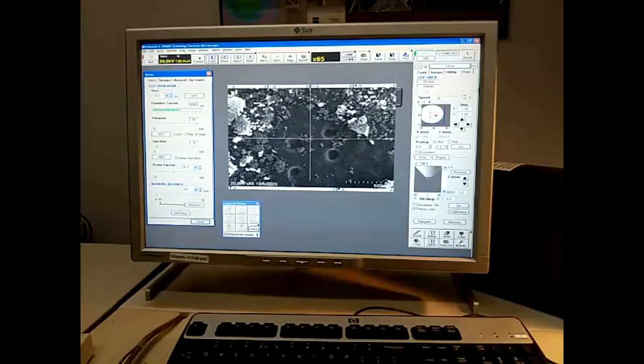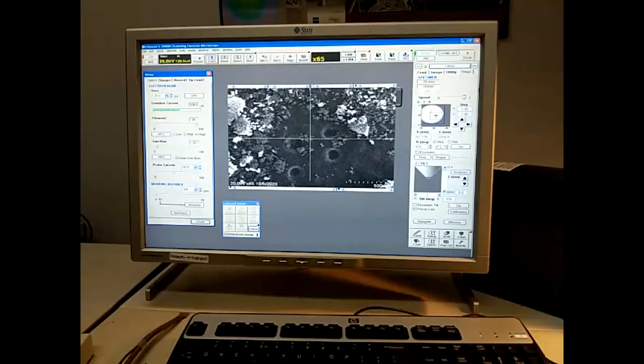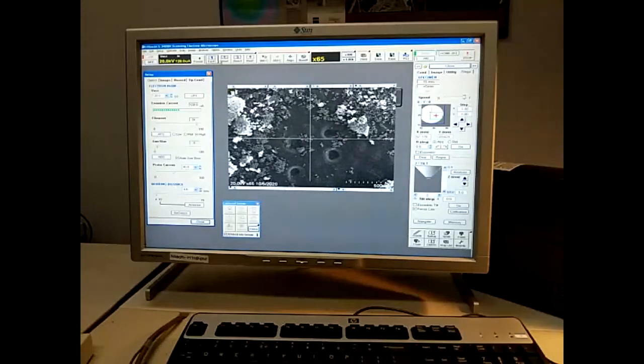Here we have the machine on an aperture setting of four, which is the smallest aperture for highest resolution available. As you can see, the maximum magnification at this resolution is 65 times. This is in fast or television type mode. If I put it on the slow mode, it gives you an idea of the crispness of the image in this low magnification setting.